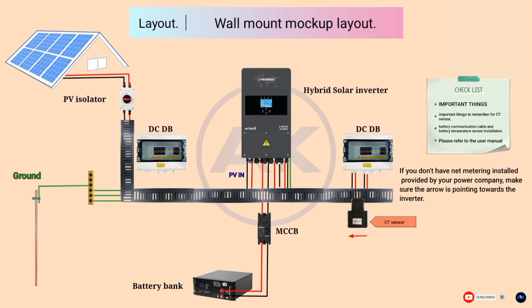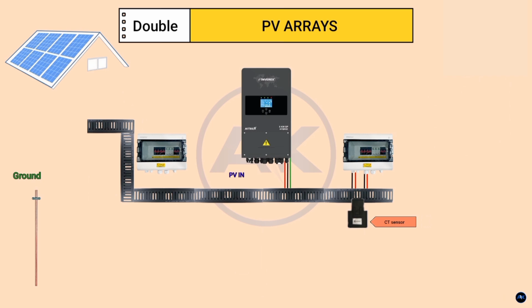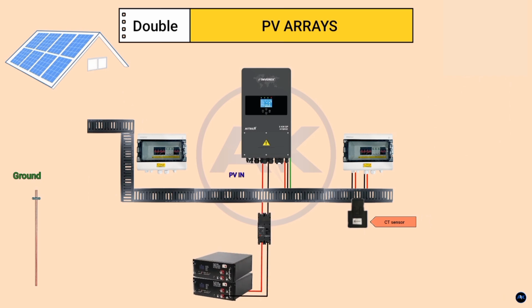So in case you are going to ask, what if you're going to use dual strings of PV array and also double the capacity of your battery bank? This is how it's going to look. We have the battery banks, 2 times 200 amp hours, and the bus bar with all the ground wires, 2 PV switches going to the PV arrays, all the wiring needed, and the CT sensor, and that's it.